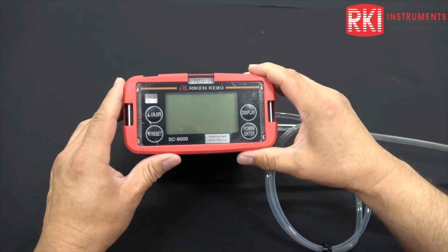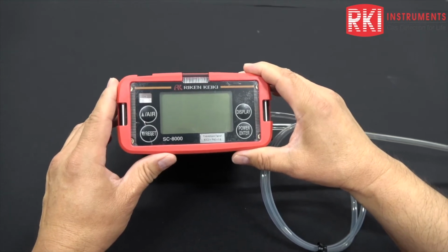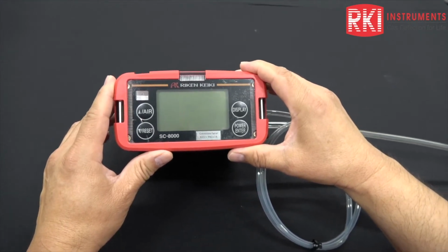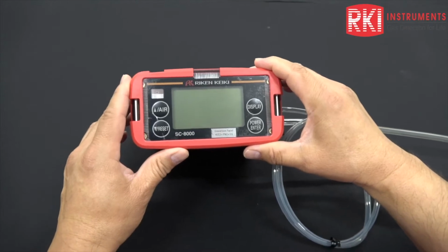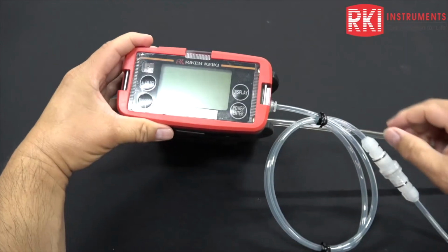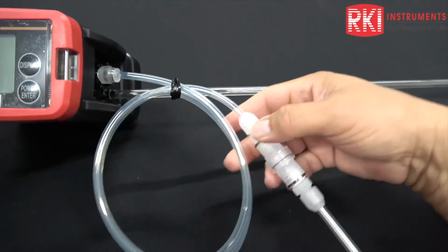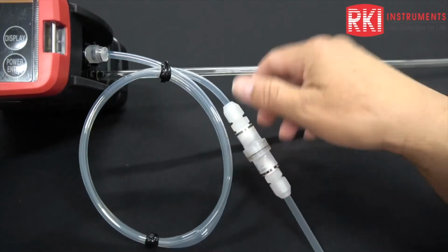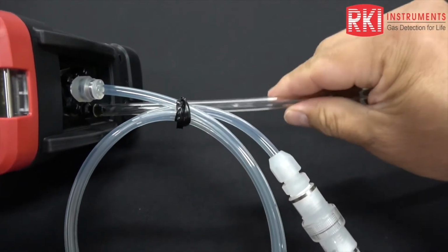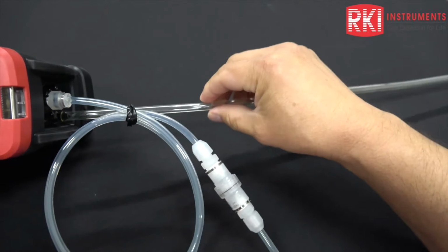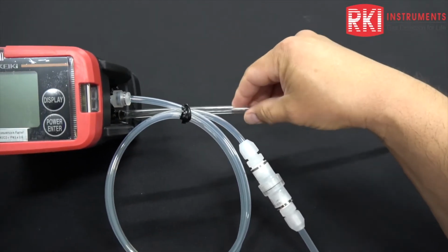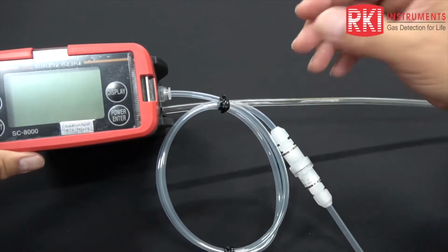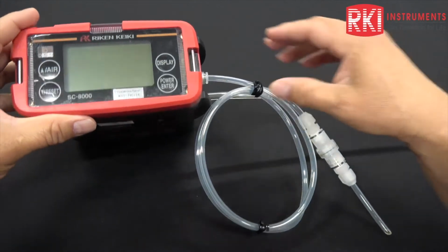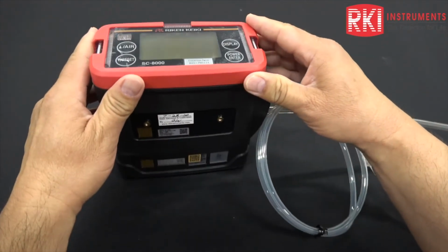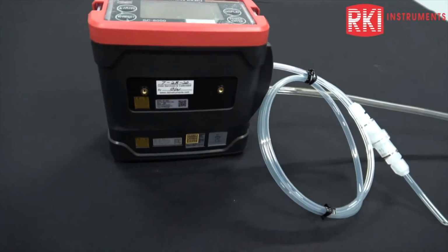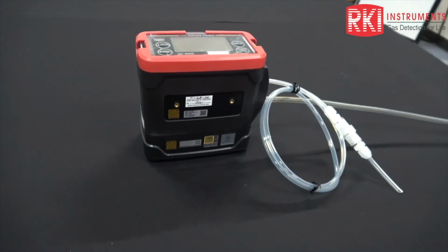This is a very sensitive sensor in this unit with a full-scale range of 0 to 500 parts per billion, or ppb. All right. We've got a little hose and probe assembly connected to the unit already. This is the inlet. And I've got a long length of tubing for the exhaust. This is just to get the phosphine away from my immediate area, away from my face and breathing zone. So that's easily accomplished as well. And then some other components that we need to look at that we're going to be using.